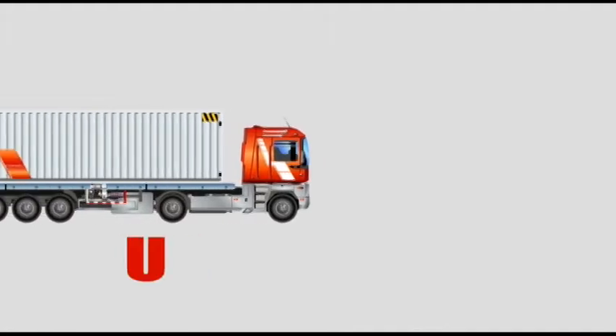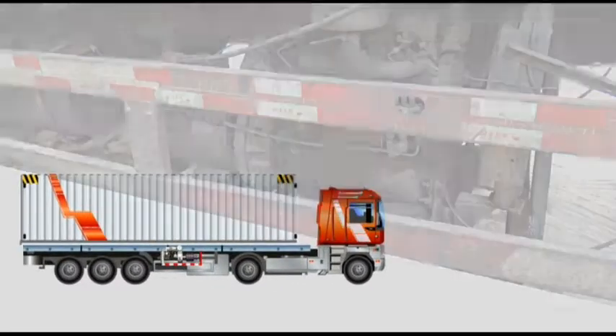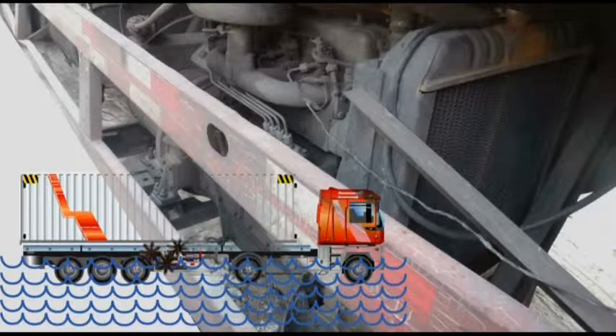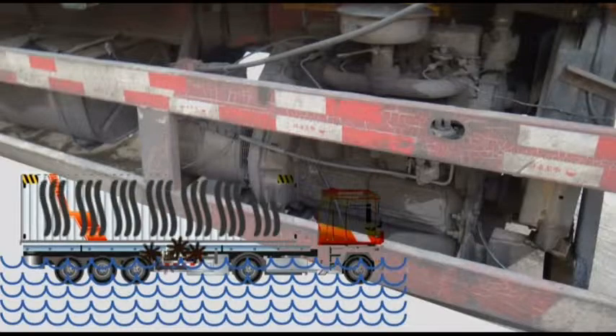The under-mount type generator is the most popular in China. However, this type of generator is not water and dust resistant. The alternator IP23 is an open type, making it prone to damage, which may affect the goods in the container.